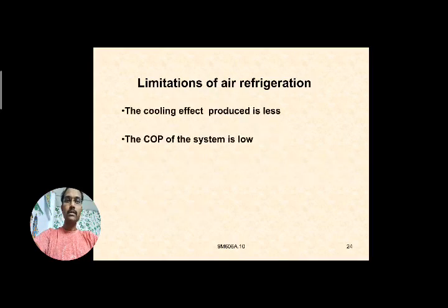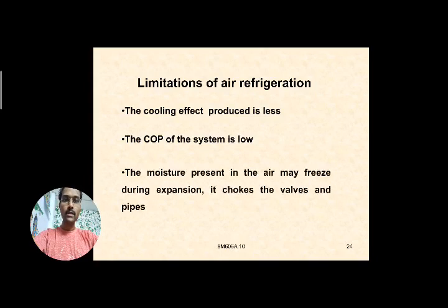Next we'll see some limitations or disadvantages. Already discussed, due to the very low COP of air refrigeration, the cooling effect produced is also less, and the refrigeration effect is less, primarily because air is carrying only the sensible heat and no phase change is taking place here. It will not carry the latent heat. That is one of the reasons why you are getting less cooling effect compared with the other refrigeration systems.